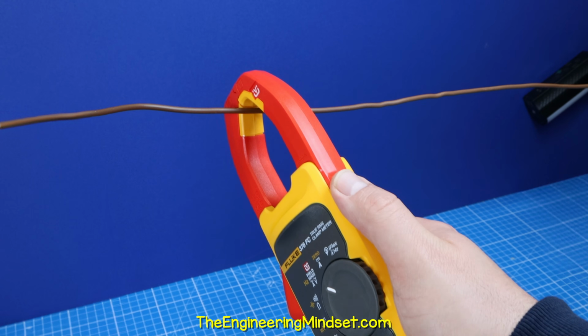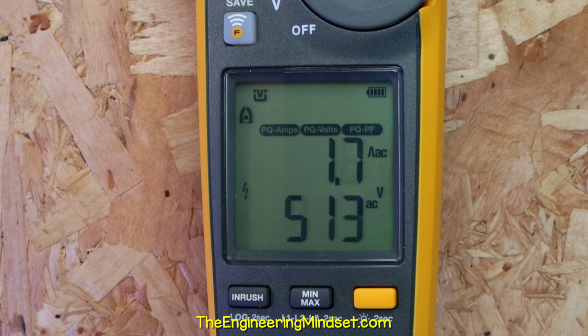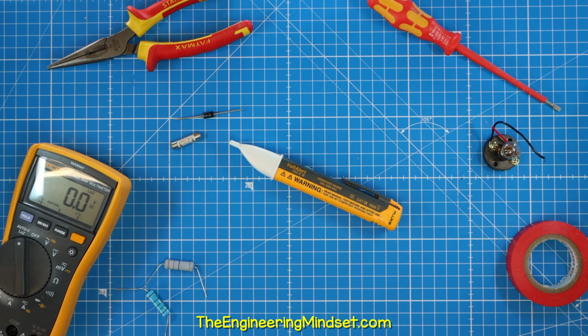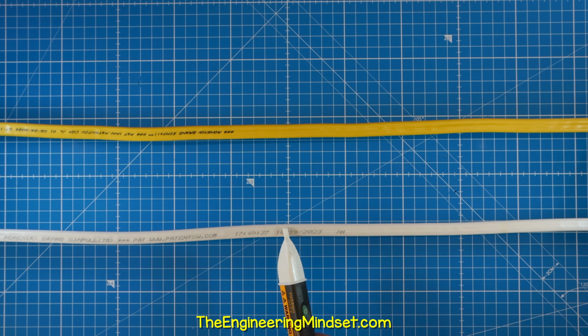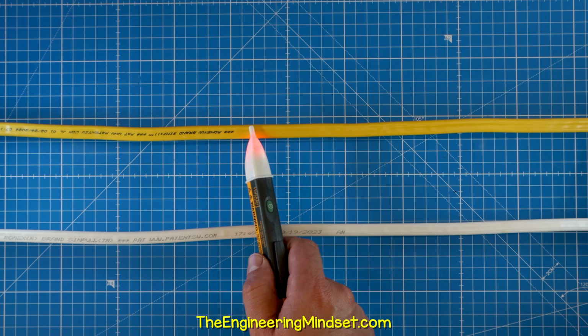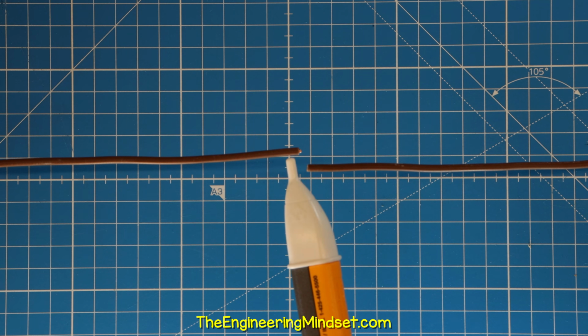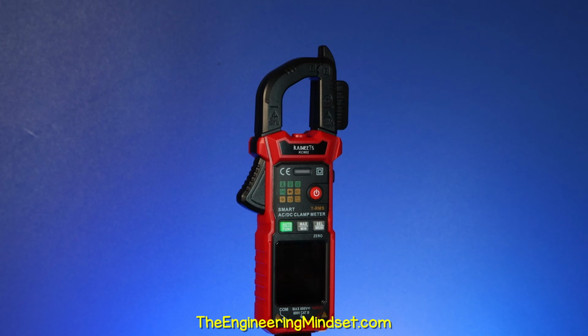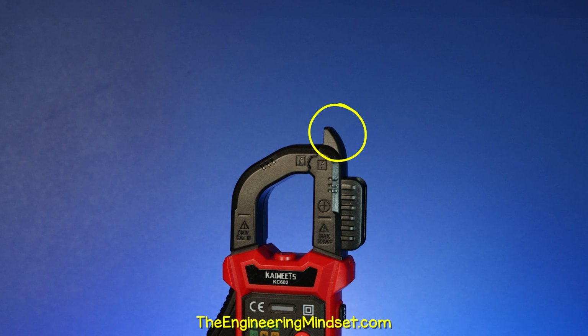We then clamp around the wire. It will then tell us the voltage without us having to connect into the circuit. A non-contact voltage detector can be used to quickly check if a wire is energized or to find a break in a wire. But many clamp meters now have this feature built into the clamp jaw.